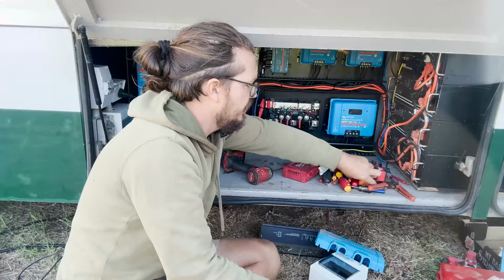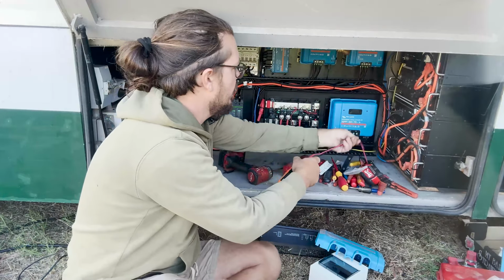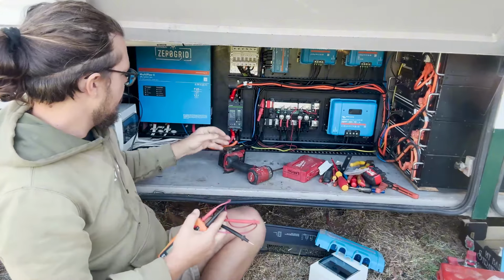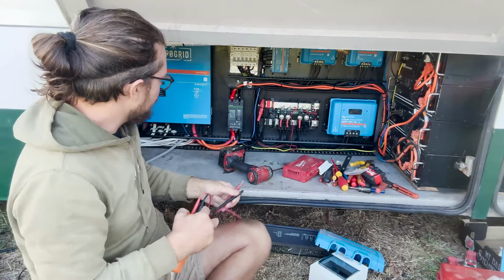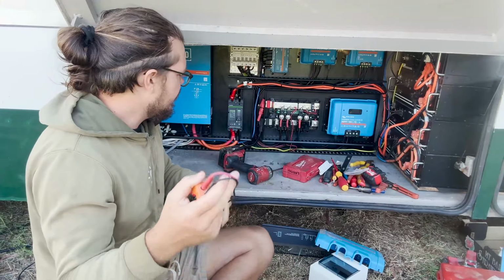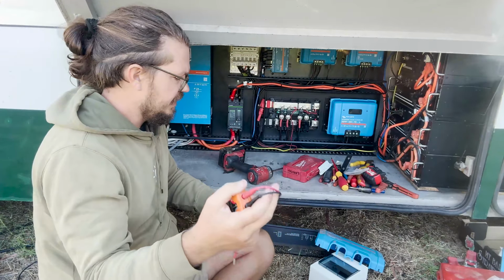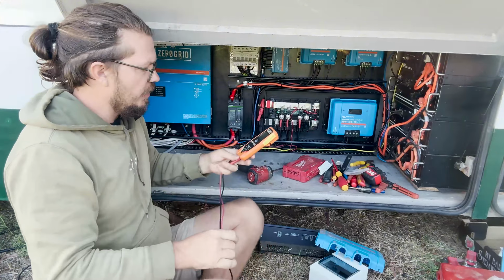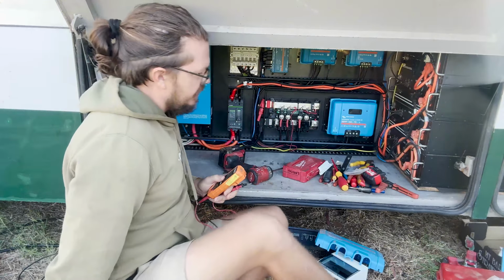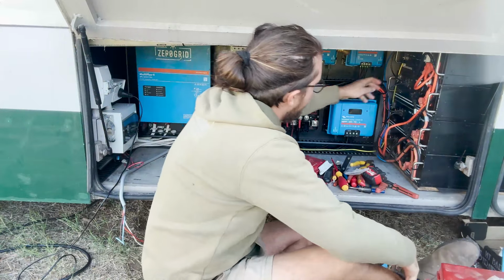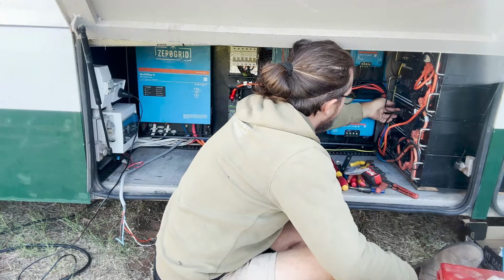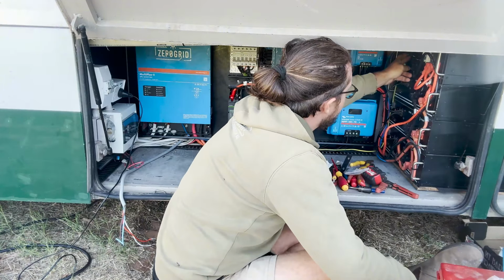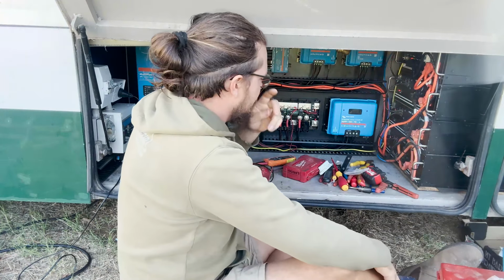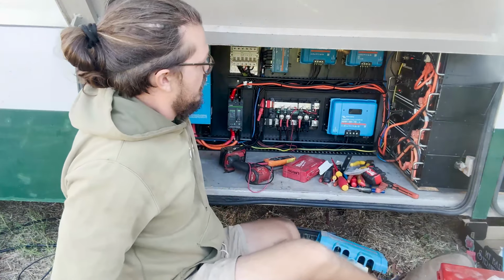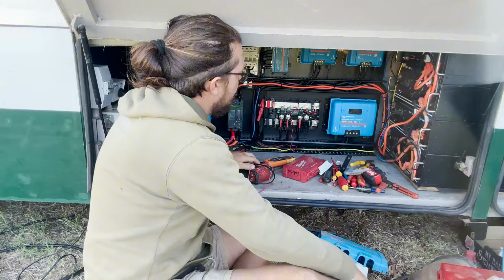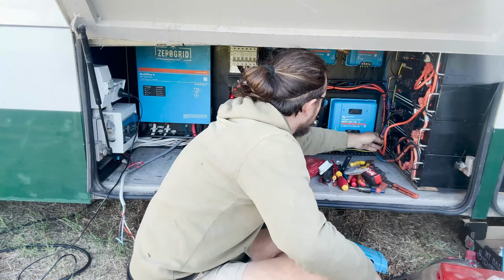At the start, we check all the connections, on the inverter too, making sure they're still good and that we haven't wiggled anything loose, nothing obvious hanging around that needs tightening. Then we can go ahead and connect our batteries or turn them on, whichever your batteries require. Some have a bit of a startup procedure, so these have a startup and they should all come on.